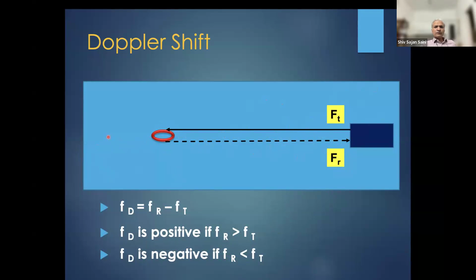Now how do we use that? We calculate it by using this formula. This 2 is because it is moving; this is taking a two-way trip. So the frequency of the transmitted signal multiplied by v, which is the velocity of the object inside, and c is the speed of the ultrasound beam, which is 1540 meters per second. Because we know this, we can calculate the Doppler shift, and because the machine knows the Doppler shift, the machine can back calculate the velocity by putting in this formula. And this is how the machine calculates the velocity of this particular structure, be it a tissue, be it a valve, or be it blood.